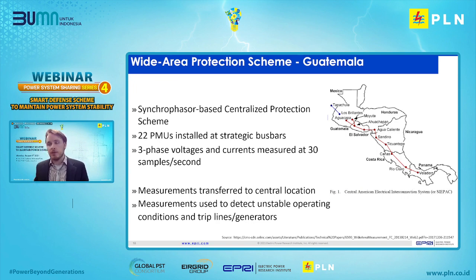And these are communicated back to a central controller, to a central location, where it performs modal analysis and oscillation analysis to determine if there are any oscillations on the grid and where the oscillations were triggered or are occurring from. Based on the detection of the oscillations, the centralized scheme then commands specific lines or generators to trip offline and thus to reduce or eliminate the oscillations. So this scheme was put in place in 2013, 8 years ago, and it has been operated a number of times successfully.